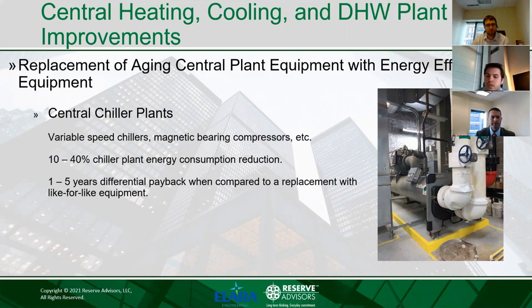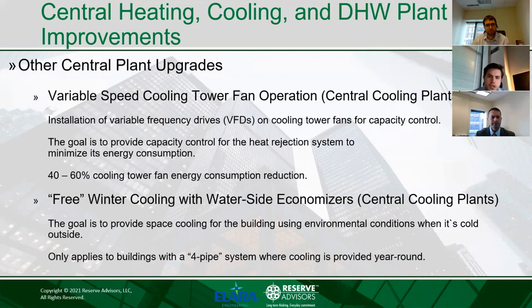For central chiller plants, higher efficiency options include variable speed chillers, chillers with magnetic bearing compressors, and with these types of projects, we typically see 10 to 40% energy consumption reduction with 1 to 5 years differential payback when compared to replacements with standard efficiency equipment. Again, in addition to energy savings, there would be additional benefits related to equipment operation, maintenance, and redundancy.